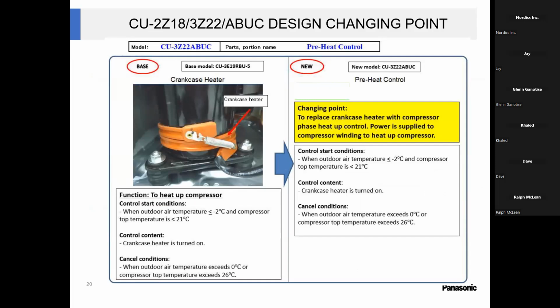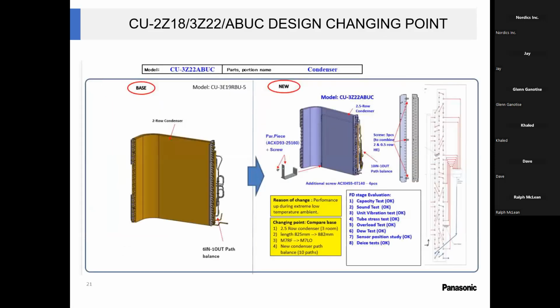So basically, we don't have any more crankcase heater on our compressors. The coil, they have significantly redesigned the coil. Basically, the old coil had just one piece. Now we have two pieces, as you can see. Maybe once I'm done with the multi-zones, I can share some pictures and go through what you will see and what you can expect from the new units, the new multi-zone condenser coil and other stuff.